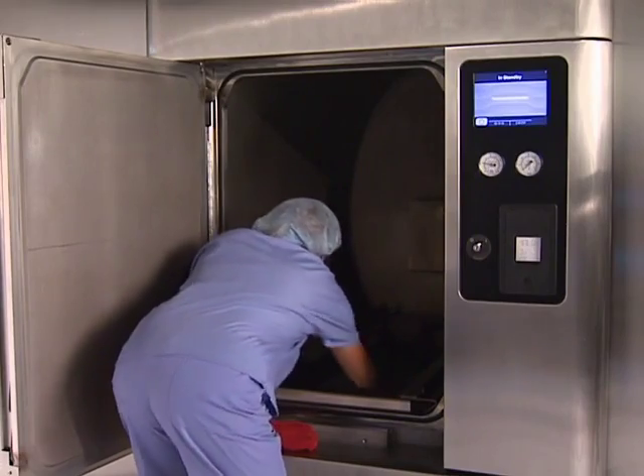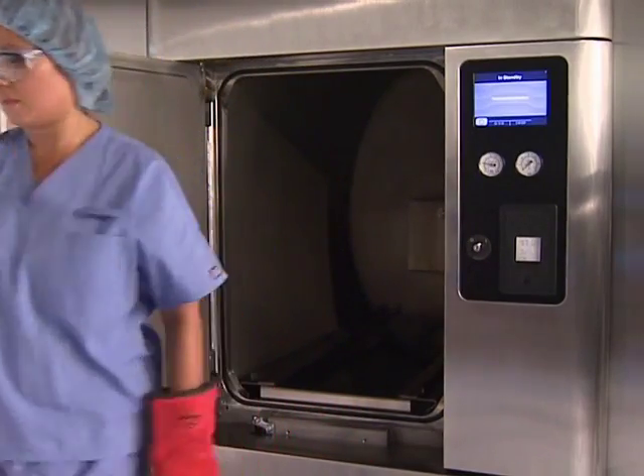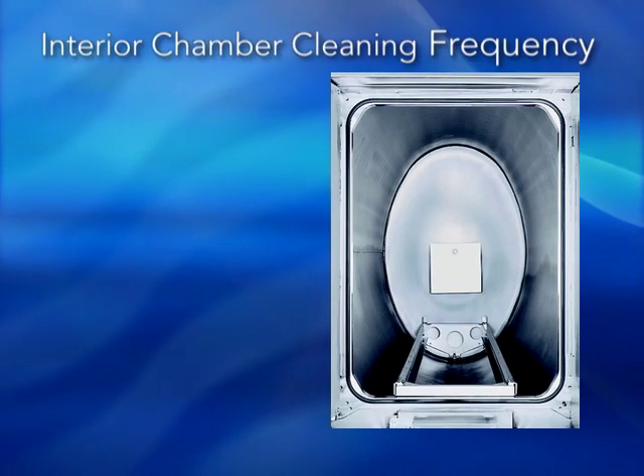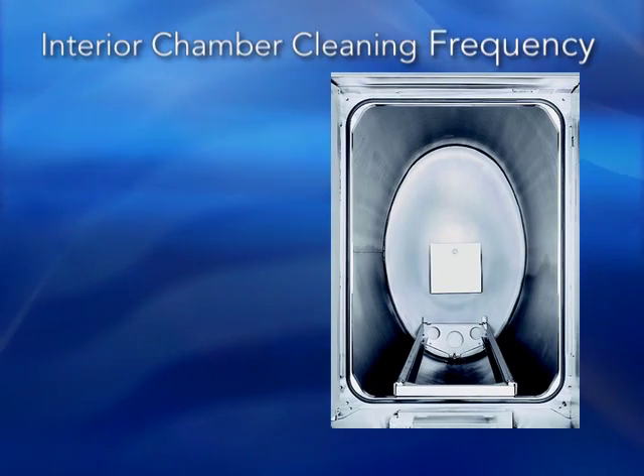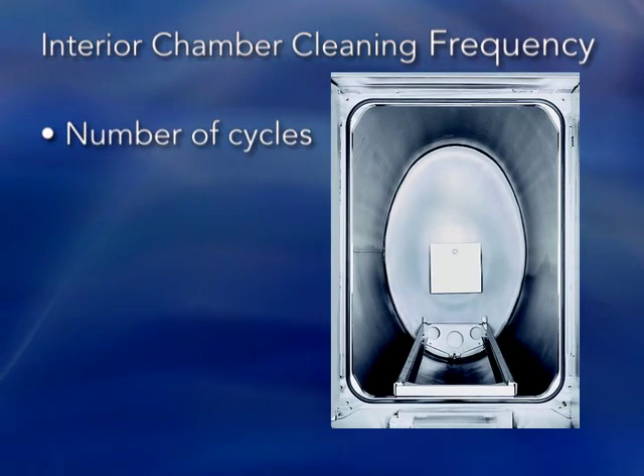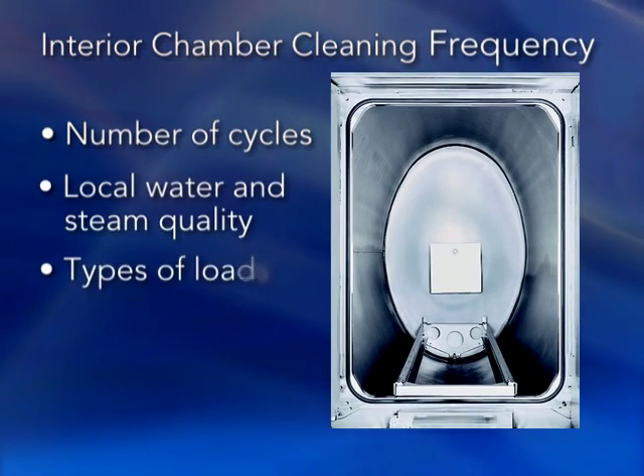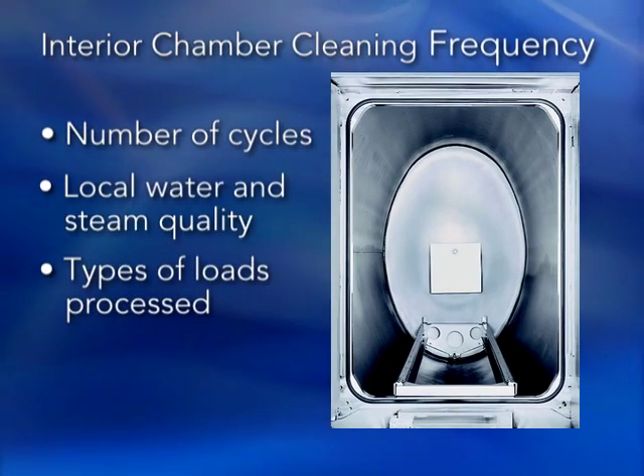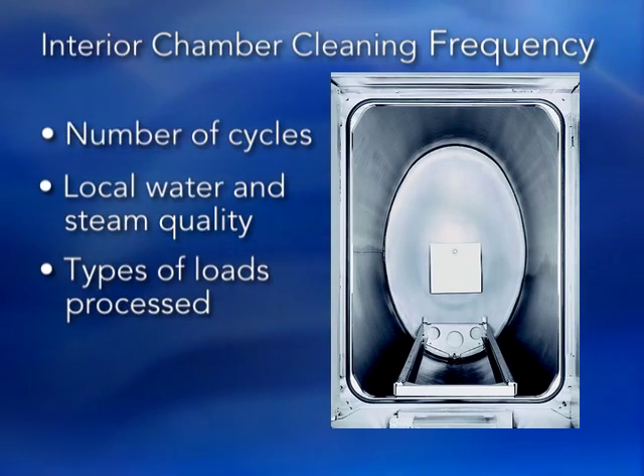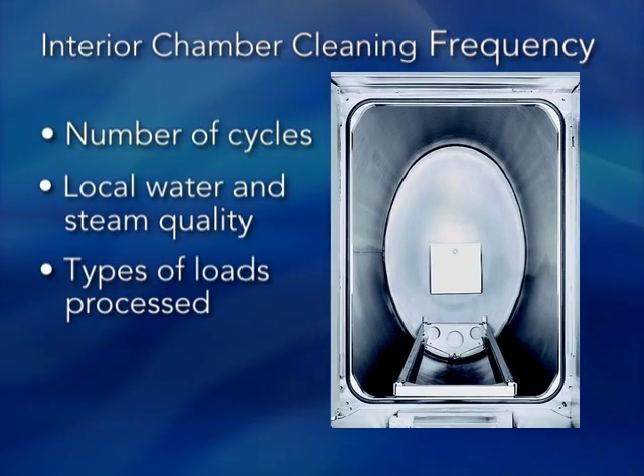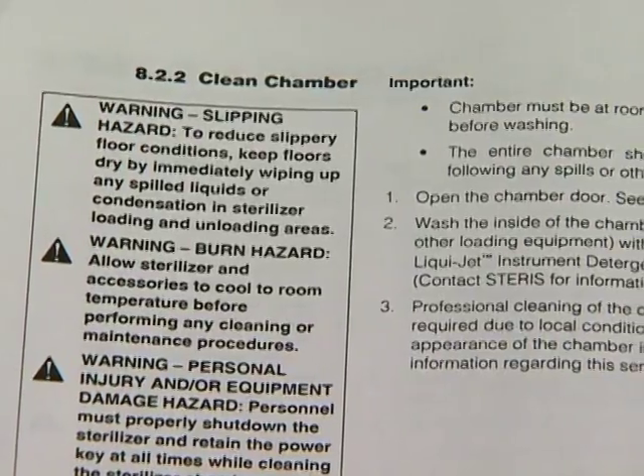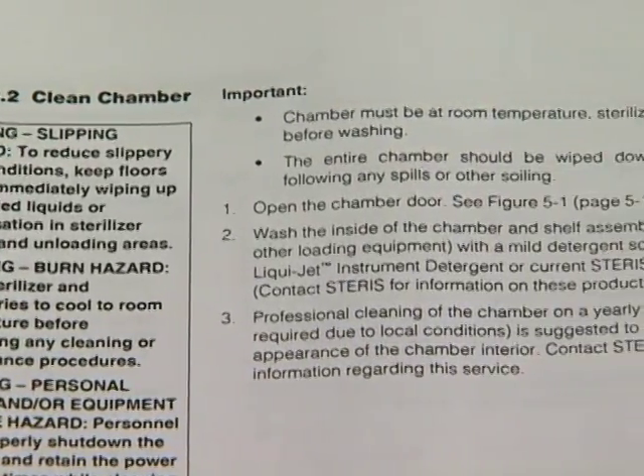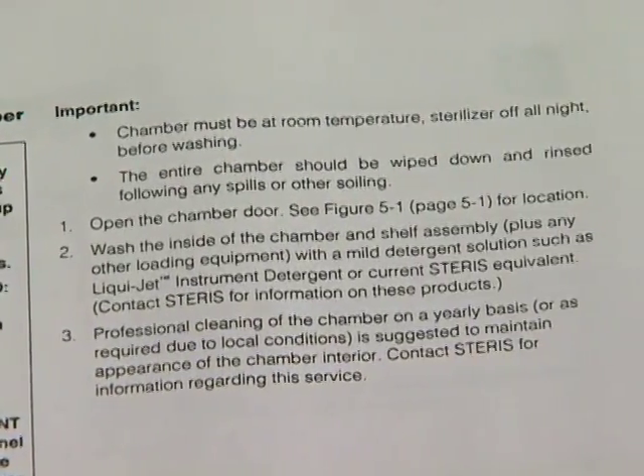It's important to clean the chamber interior whenever spills or other soiling have occurred. The overall frequency of chamber interior cleaning will depend on the number of cycles run, local water and steam quality, and types of loads processed. The chamber interior should be cleaned as frequently as necessary to maintain its original appearance. Follow the instructions in Section 8 of your Evolution Sterilizer Operator Manual.